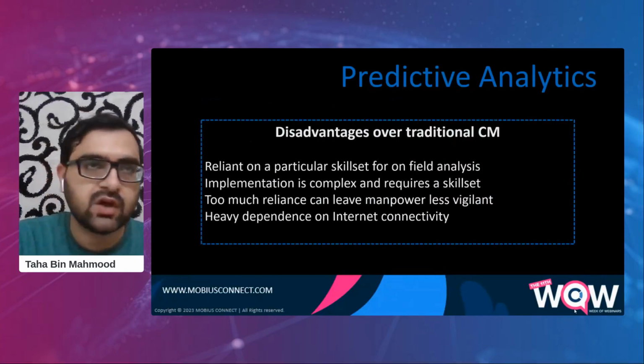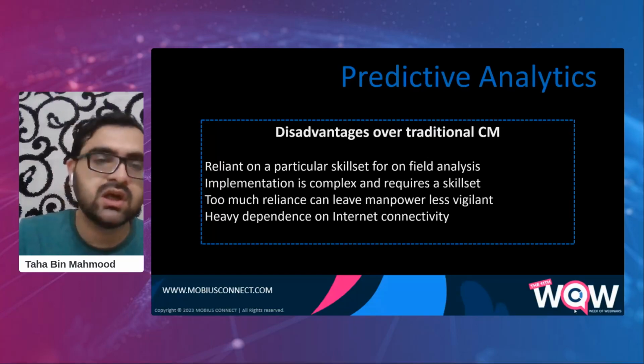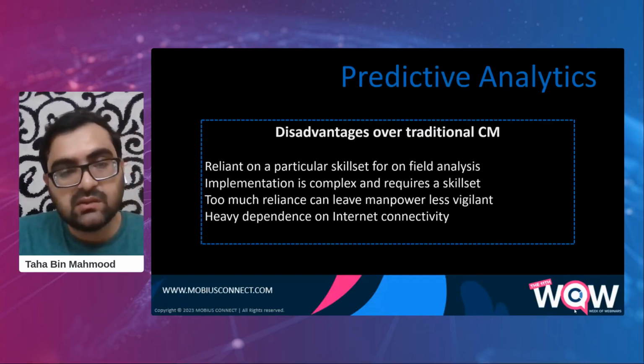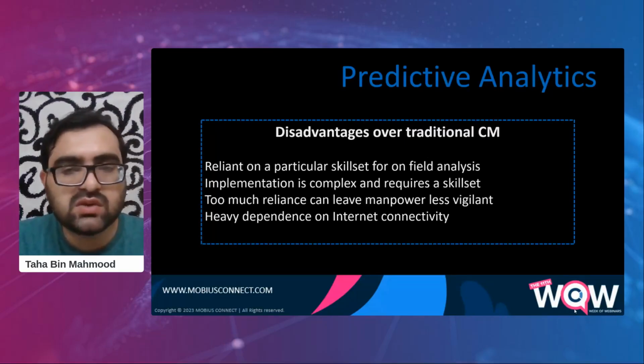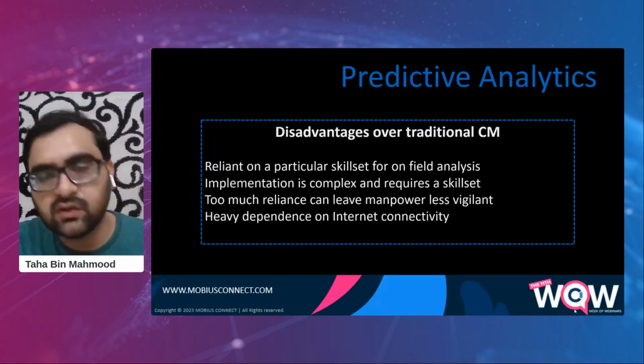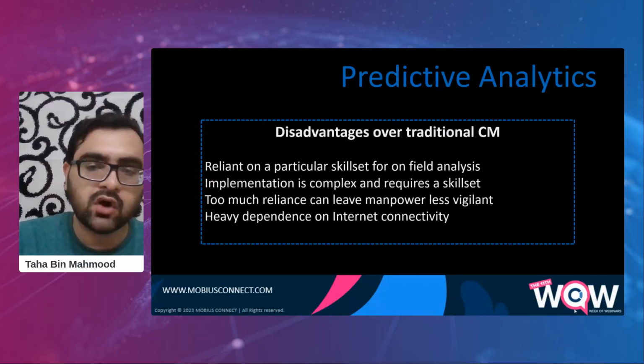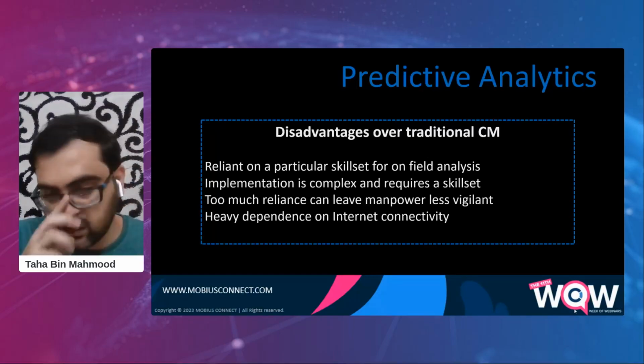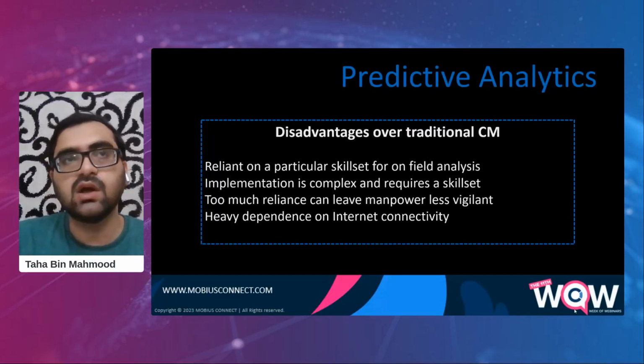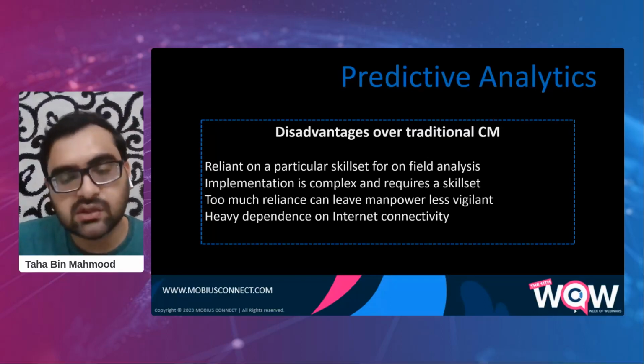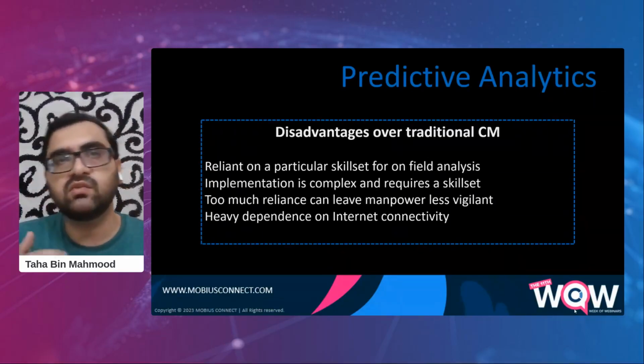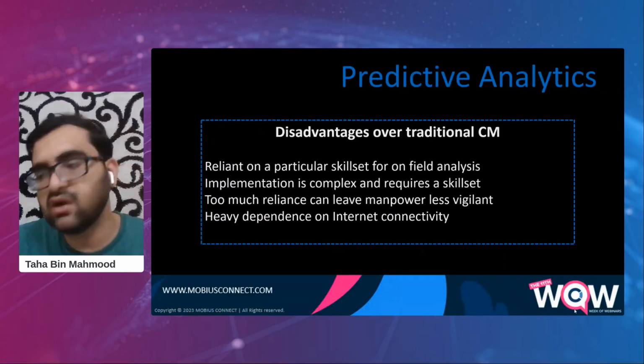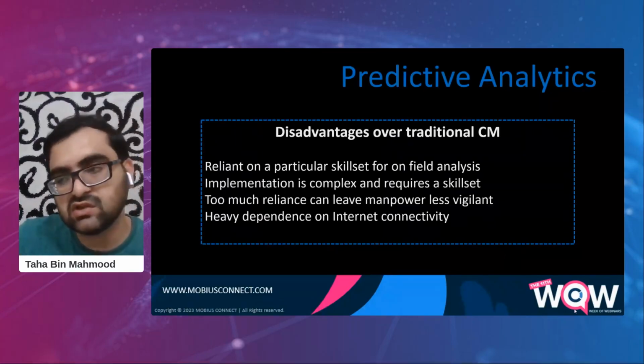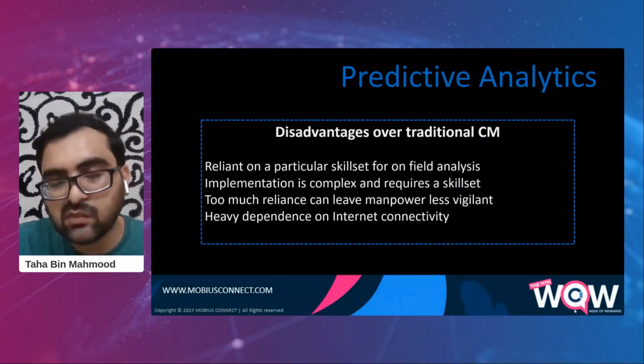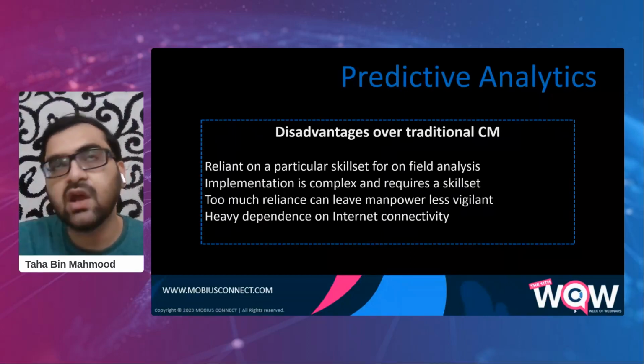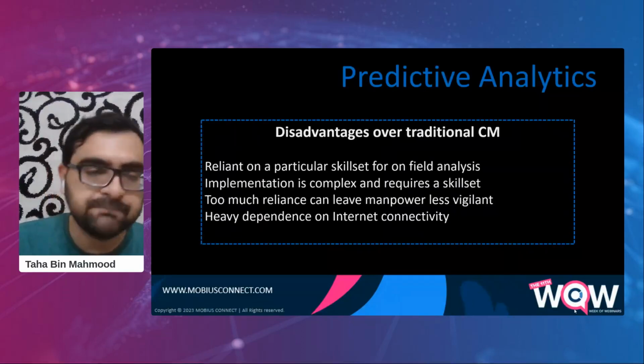Now, when we talk about advantages, we should also touch upon the disadvantages. The main disadvantage is that you cannot eliminate human intervention altogether. You still have to rely on on-prem or on-field analysis by an expert, especially when you have to dive deeper into actual condition monitoring techniques. You can trigger an alert that bearing vibration or temperature, or lube oil temperature, has increased, but you might still require on-prem analysis, especially for vibration analysis and lube oil analysis, to be carried out by the site team.